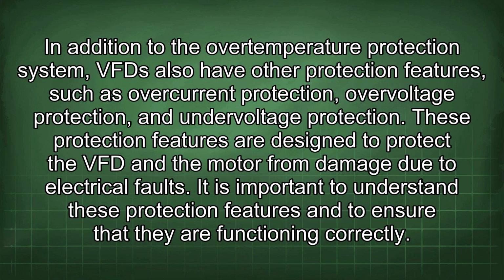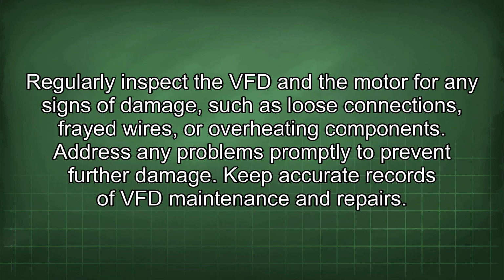In addition to the overtemperature protection system, VFDs also have other protection features, such as overcurrent protection, overvoltage protection, and undervoltage protection. These protection features are designed to protect the VFD and the motor from damage due to electrical faults. It is important to understand these protection features and to ensure that they are functioning correctly. Regularly inspect the VFD and the motor for any signs of damage, such as loose connections, frayed wires, or overheating components. Address any problems promptly to prevent further damage.